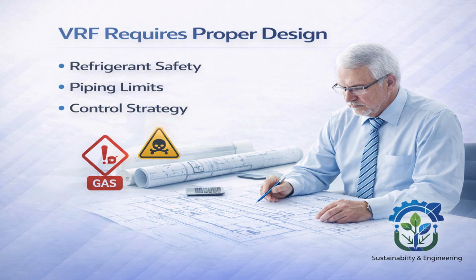If we ignore this, indoor air quality is affected, occupant safety is compromised, and authorities may reject the design. This is why room volume calculations, leak detection, and ventilation strategies are not optional in VRF design. Second is piping limits. VRF systems have strict piping limitations. These include maximum total piping length, maximum vertical height difference, and maximum distance between outdoor and indoor units. If these limits are exceeded, oil return is affected, compressors work harder, and system reliability drops. This is why VRF piping cannot be routed randomly. Pipe routing must be planned early, coordinated with architecture and structure, and verified against the manufacturer's limitations. Ignoring piping limits is one of the most common VRF design mistakes.